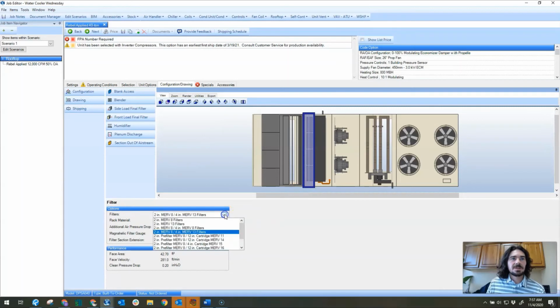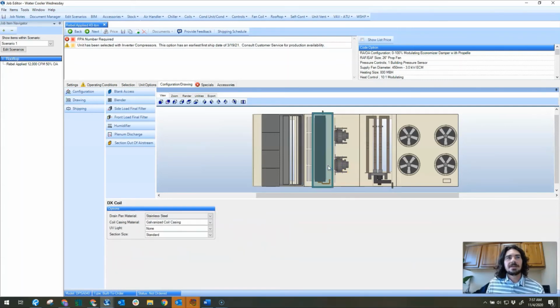Filter section, we can do a lot of different things. I like to select as a standard MERV 8 with a MERV 13 pre and post arrangement. You can see it's configurable to do some other arrangements as well. I'm going to add a 1/2-inch pressure drop here for this selection. And then for the coil, we see we've got a galvanized or steel option. I'm just going to leave it as galvanized. You can do UV light if you want, but in this case I'm going to leave it alone.